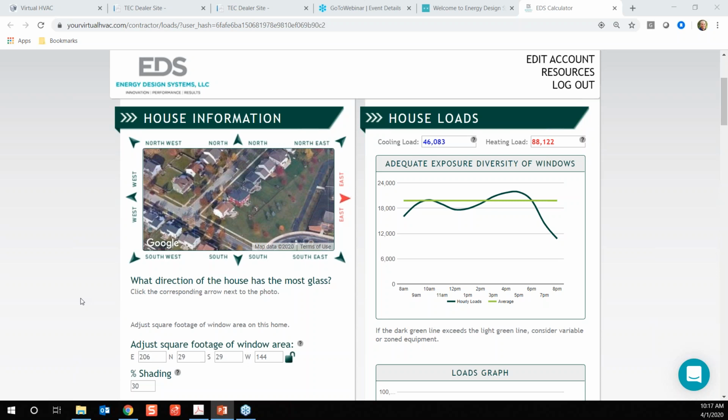I mean, you could use it for residential new construction, but there's 2 problems with using it on new construction residential. One, it's not going to be able to find your address yet because your address doesn't exist. So you have to force everything in manually, which is fine. But 2, residential new construction, you're also going to need an ACCA Manual D for duct design. So you might as well just use a different tool that does Manual S, Manual J, and Manual D all in one crack, such as Wrightsoft. But for quickie stuff that's existing, on furnace, boiler, air conditioner, heat pump changeouts, this tool works just fine.